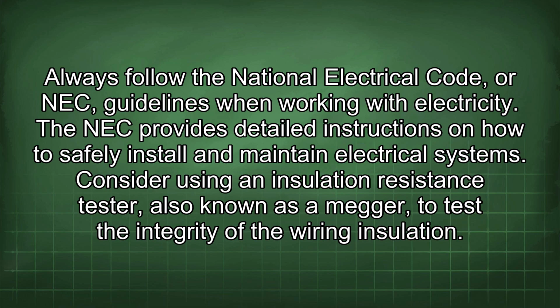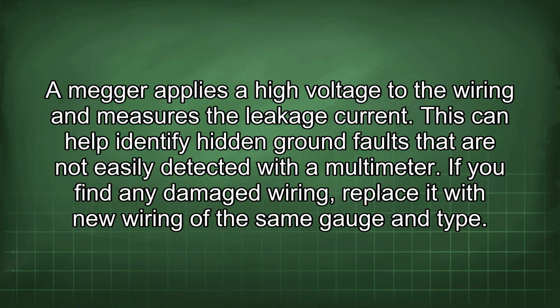Consider using an insulation resistance tester, also known as a megger, to test the integrity of the wiring insulation. A megger applies a high voltage to the wiring and measures the leakage current. This can help identify hidden ground faults that are not easily detected with a multimeter.